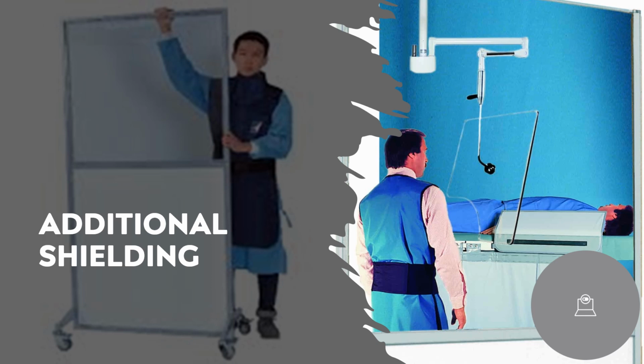Additional shielding, that's going to be on page 303. You can have clear secondary acrylic barriers, and they should have about 30% of lead by weight. They should be shatter resistant, extend 2.1 meters up, and can be available anywhere from 0.3 to 1.0 millimeters of lead equivalent. There can also be clear overhead barriers, usually used in the cath lab, and they have to have 0.5 millimeters of lead equivalency.